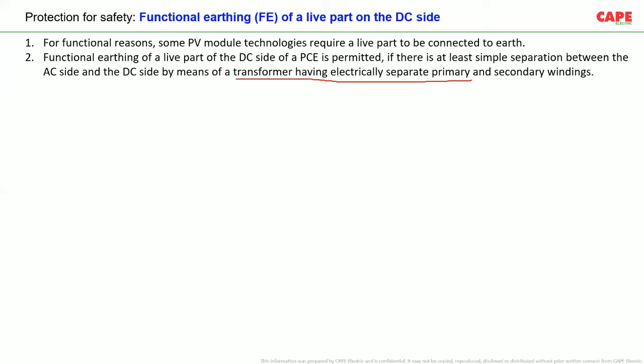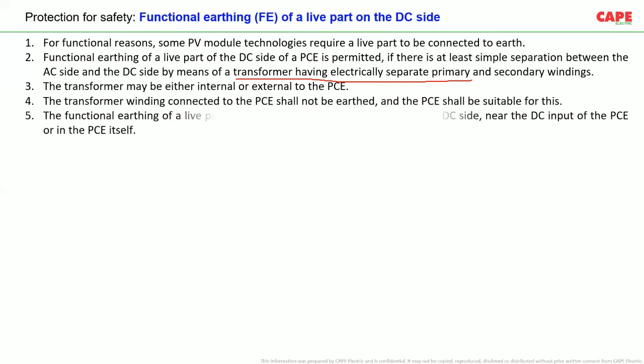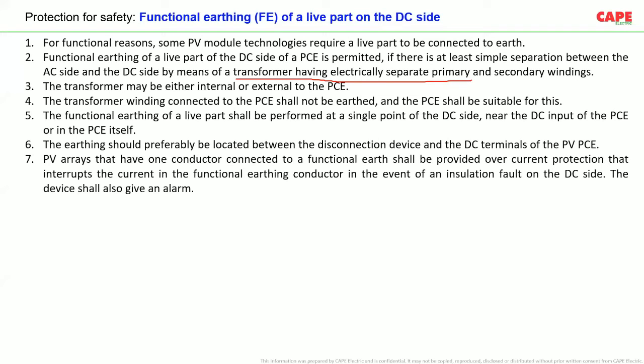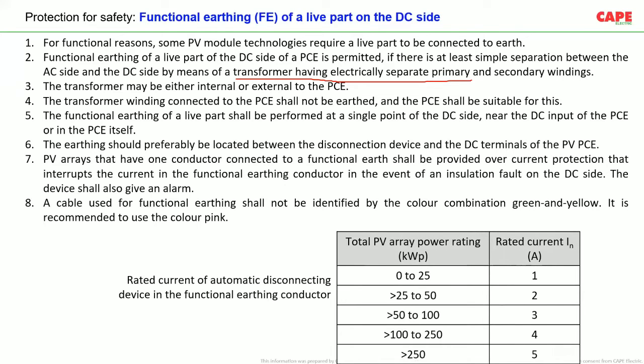If you don't have electrical separation, and I'm sure most of the time nowadays the market is using PCE without electrical separation, because without electrical separation is cheaper, we have to adopt some additional safety measures. So all these conditions have to be fulfilled in order to have a safe system. As I said, through the functional earthing, depending upon the capacity of the installed PV array, you are supposed to measure the current and you are supposed to disconnect.